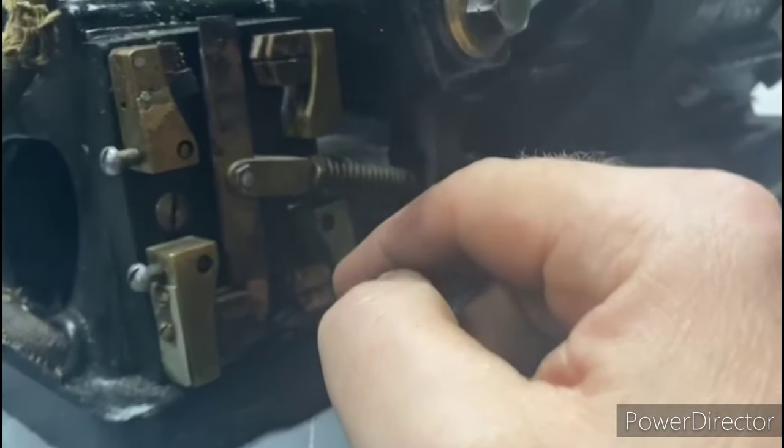I'm making some good progress on these stator windings. I'm using two-part epoxy and I've gone ahead and put it wherever the insulation was compromised — in some areas it was missing completely. While that's drying, I'm focusing on this junction where these two wires come out. The gentleman told me this motor does not run, and I could see where somebody tried to make a repair. I removed that vinyl electrical tape, and the first thing that caught my attention was this wire, which goes to the right carbon brush — it's only held on with about three strands. The rest of them are broken off. That in and of itself could have been a reason why the motor wasn't running. I'm going to go ahead and solder on a new lead using my new old stock cloth-covered wire. The other wire over here, which is solid core, seems to be okay — all the insulation is on there. So I'm just going to clean that and put a coat of insulation varnish on there and preserve that one.